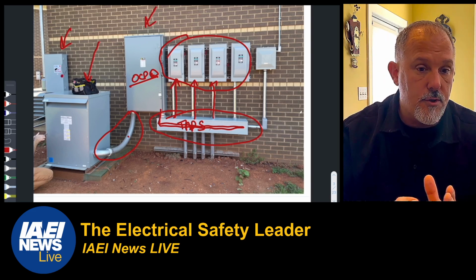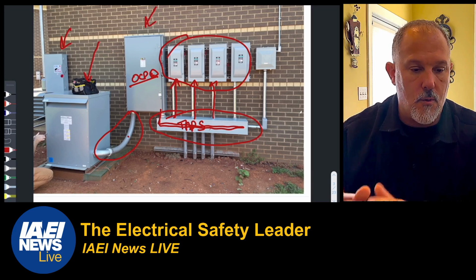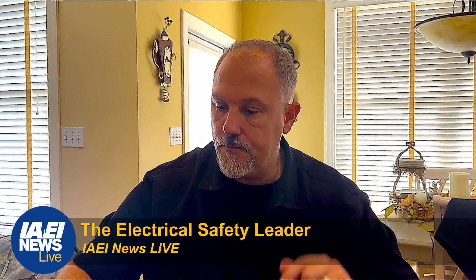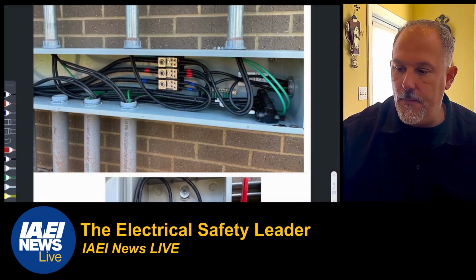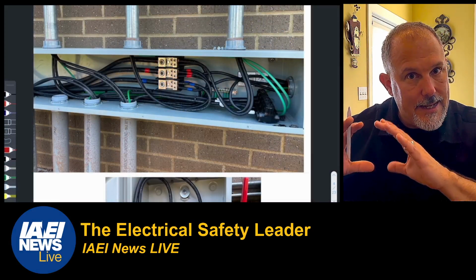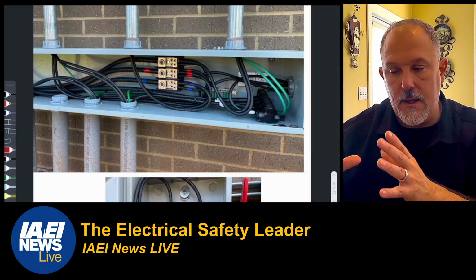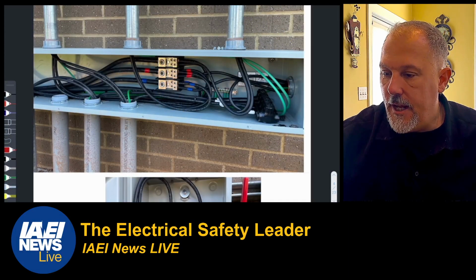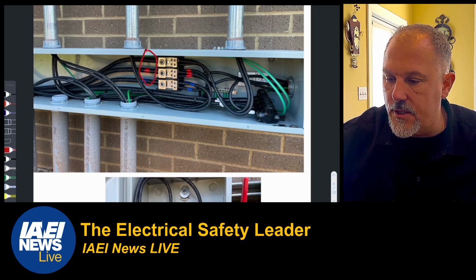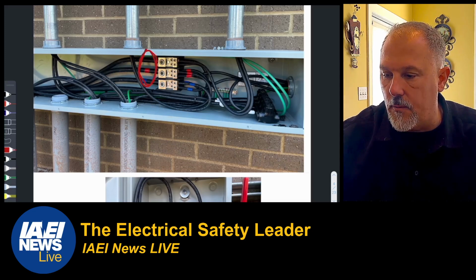And in Article 240, we'll walk through the requirements. So now, here, I'll show you this too. So now, this is a look inside of the trough. And you'll notice these are the conductors that are coming from the secondary of that transformer.